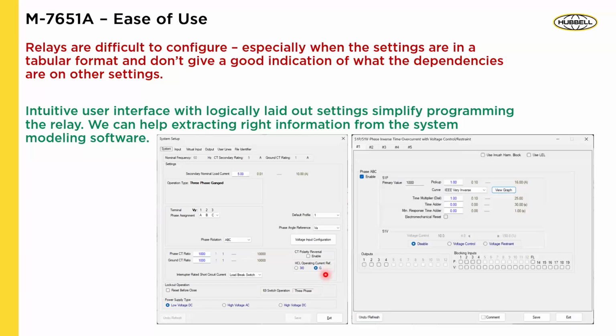Same with, let's say, a typical 51P element, right? That's your timed overcurrent protection. You see the pickup, the curve selection, time dial, time adder, minimum response time, and electromechanical reset. And you can even see the graph and how it's laid out, right? And then we say, okay, 51V, if you want to do the voltage control or restraint, that's a separate category. And then you could disable it, you could select this. So it's very easy for you to follow through.